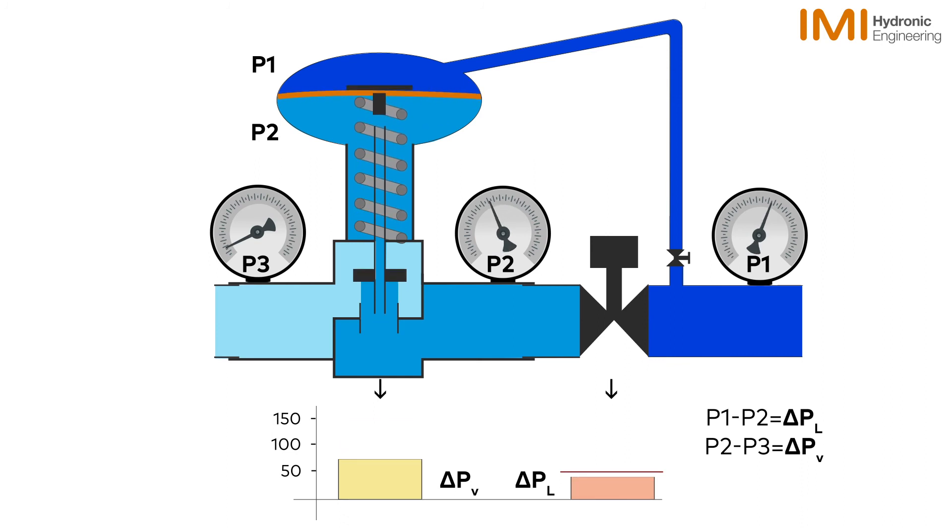It can maintain this control until the point where P1 reduces below the minimum required differential pressure for the circuit. Watch again as we see the valve reacting to changes in available pressure.